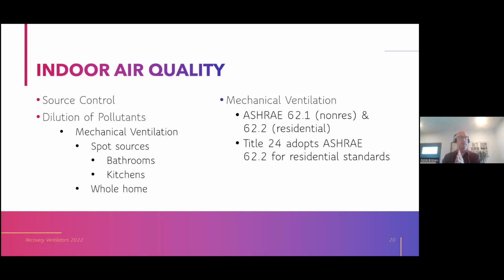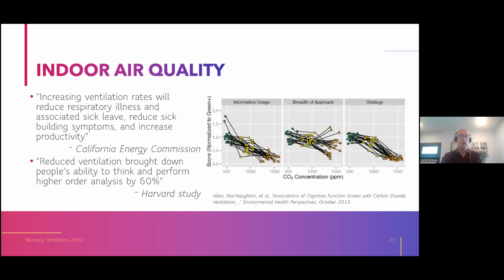So under the category of mechanical ventilation, then, we've got the need for spot source dilution, that's bathrooms, kitchens, and we've got the need for whole home dilution of pollutants. That's where the energy code comes in and requires whole home continuously operating mechanical ventilation, which we'll get to in a minute. ASHRAE standards 62.1 and 62.2 address this need for mechanical ventilation in particular. 62.1 is non-residential, 62.2 is residential, and then Title 24 effectively adopts these standards and puts them into the Title 24 code with a few minor adjustments. So this is code in our state and 3C-REN territory that we have mechanical ventilation.